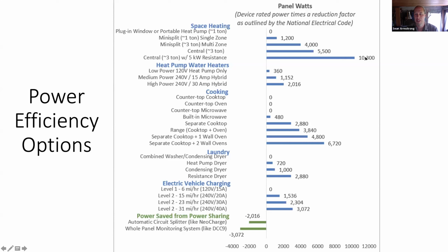Here's if you have resistance heating, 10,300 watts. Here's the heat pump water heaters: the low power ones I showed you are 360 watts on your panel, and the high power one is 2000 watts. There's also a diversity factor where you multiply the wattage by 0.4, and that's what the panel sees. So these wattages don't line up exactly with what I showed you earlier—these are the ones the panel sees according to the National Electrical Code.